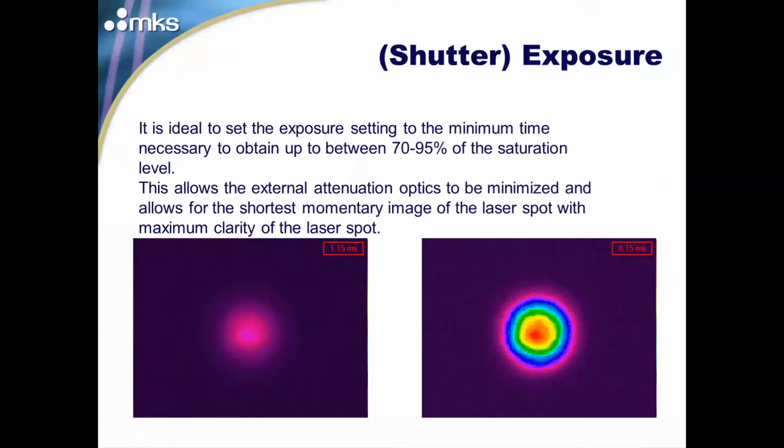If your laser signal is similar to the left, where that was about 10% of the dynamic range, then you're going to have a lot more variability. Some applications, that's all the signal you're going to be able to get, and there are some things you can do later on to make up for that. But try and get as much peak signal as you can.